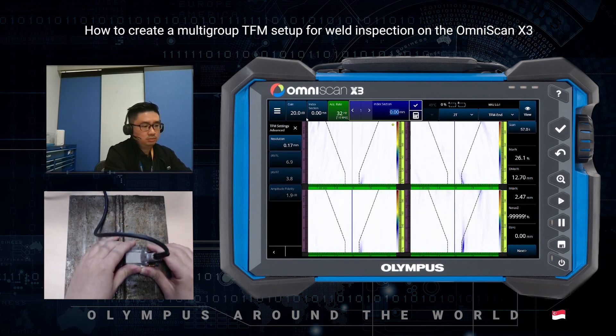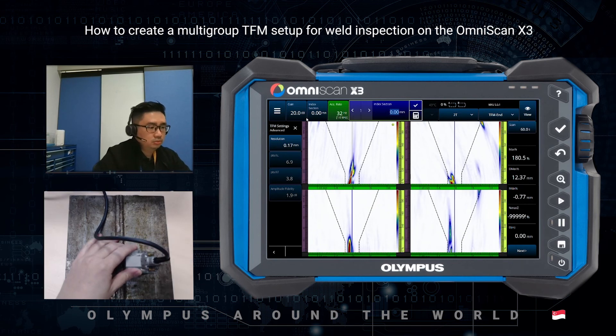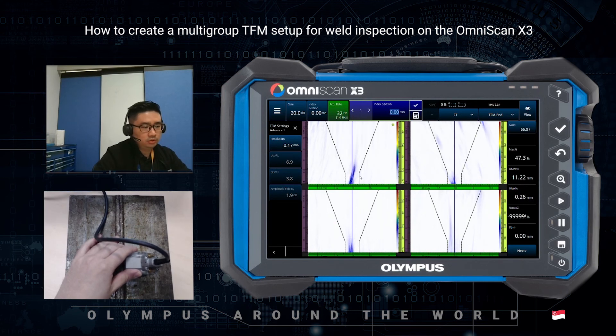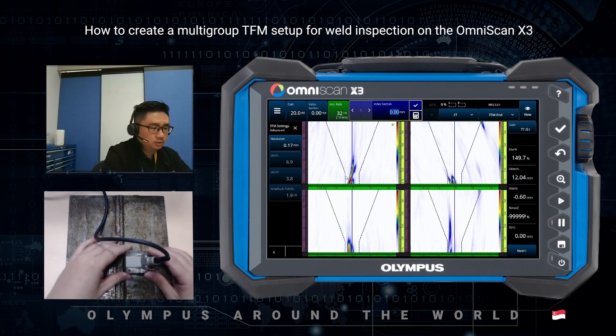As we come over here — we see a defect on the root. We can see it from the TT and 4T groups. The TT will give you the direct hit and the best signal.